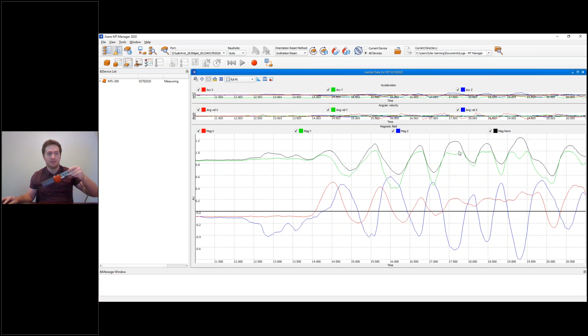First, I'm going to show in our MT Manager the magnetic distortions in the magnetic field data. As you see, I have an MTI 300 mounted to this steel plate, and as I move the sensor around, the black line moves pretty crazily with the motion of the sensor. That's because the steel plate is affecting the magnetometer's ability to measure the Earth's magnetic field.